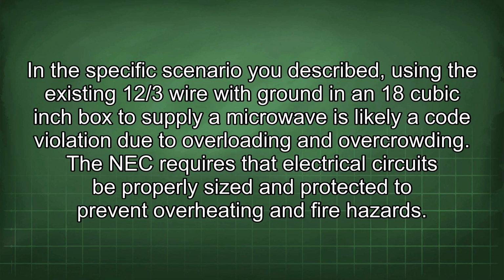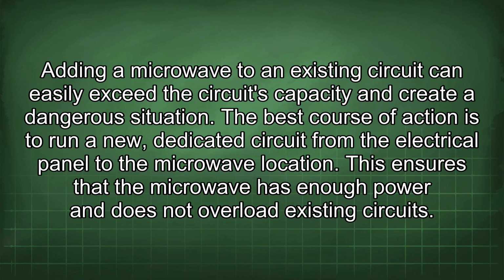In the specific scenario you described, using the existing 12/3 wire with ground in an 18 cubic inch box to supply a microwave is likely a code violation due to overloading and overcrowding. The NEC requires that electrical circuits be properly sized and protected to prevent overheating and fire hazards. Adding a microwave to an existing circuit can easily exceed the circuit's capacity and create a dangerous situation.